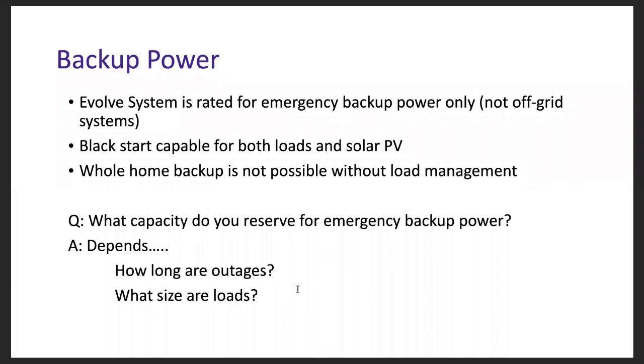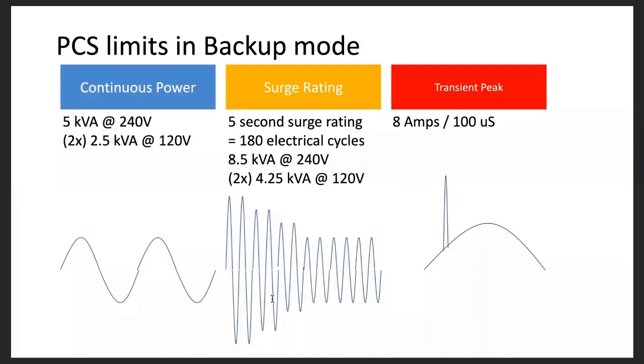Well, it depends. How long are your outages and what size are the loads? Just a quick review of what's listed on the data sheet on our website for the Evolve. The inverter has some limits for different types of voltage performance. So for continuous power, as far as serving loads, continuous power again is 5 kW or 5 kVA. 20.8 amps on each phase, so it's 2.5 kVA on each phase. So the backup loads panel needs to be balanced.